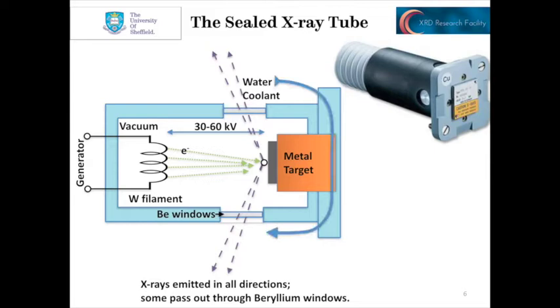As we said, this process generates an awful lot of heat as well. So we need to continuously cool the X-ray tube with water — typically in the region of 4 to 6 liters per minute. There is a serious need for cooling of these devices to prevent them from melting down.